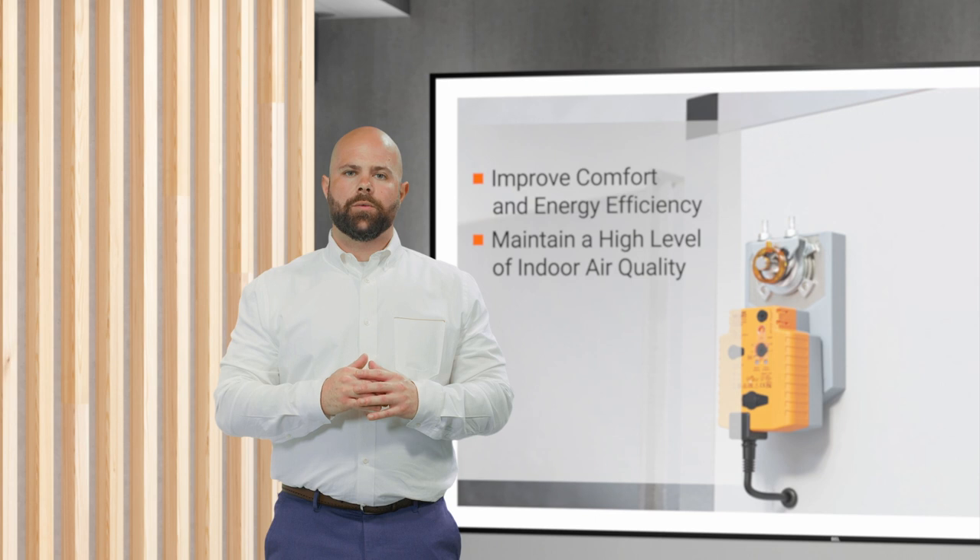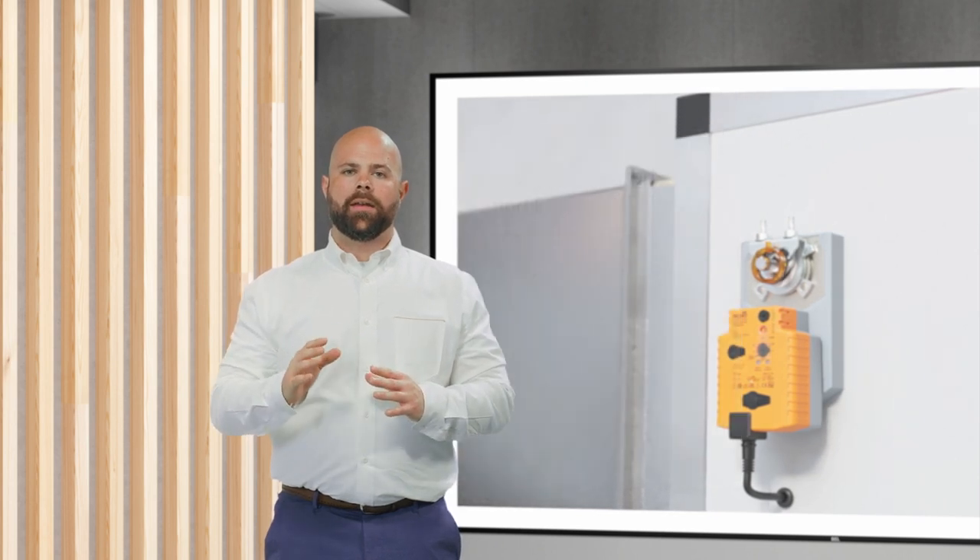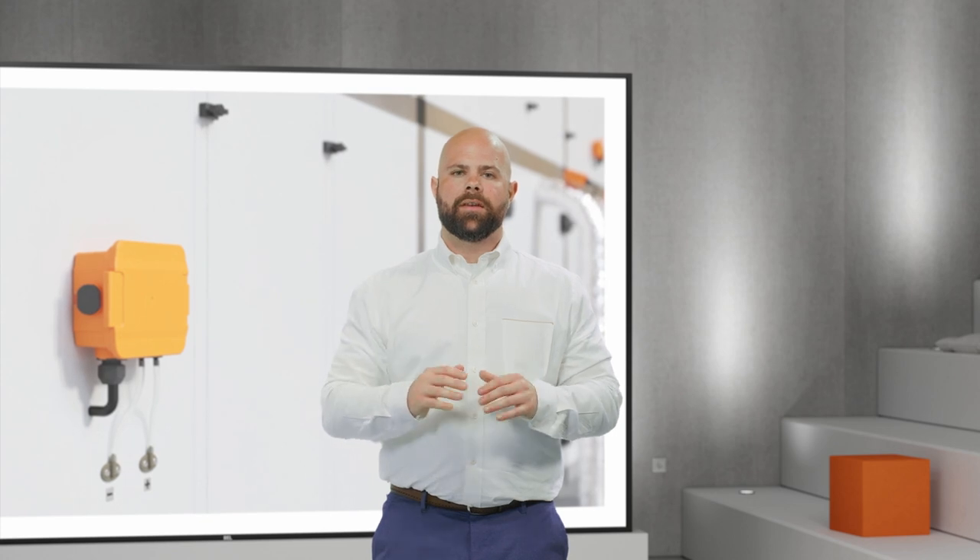With these changes, we believe you can help bring your building back to its originally intended design, or better yet, make incremental changes to improve upon that. Let's take a look at a case study from one of our customers in Calgary, Canada. They built a state-of-the-art facility that was extremely energy efficient. Of course, they installed our energy valves throughout the entire building. We were able to gain insights from our valves that allowed us to reduce the pump speeds, increase the delta-Ts, all while maintaining thermal comfort.